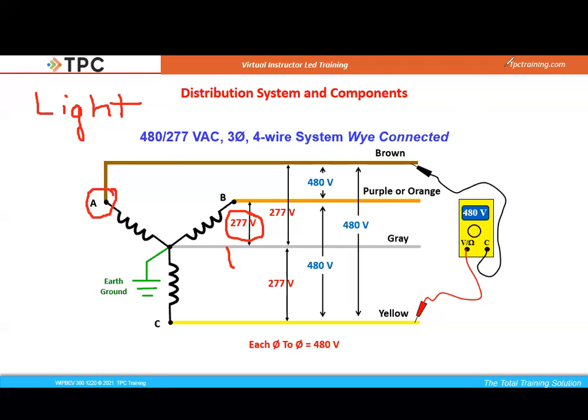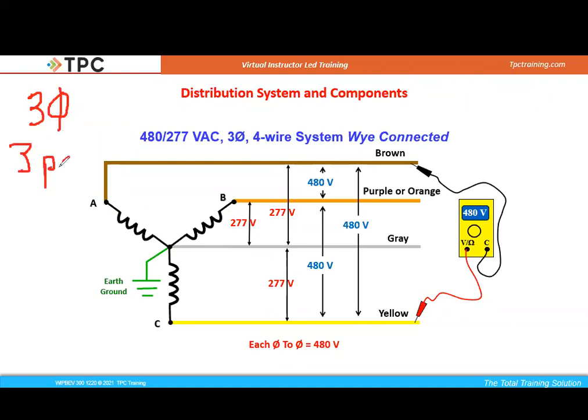And so a couple things I do want to mention about that is that if I did have that three-phase motor and I did not need my neutral, I'd be using a three-pole breaker. And I would put in phase A, phase B, phase C off that three-pole breaker. If I wanted some single-phase lighting, no problem. Put in a single-pole breaker and come off any phase with an energized conductor and then my neutral, and I would get my 277. So some important things to think about here.